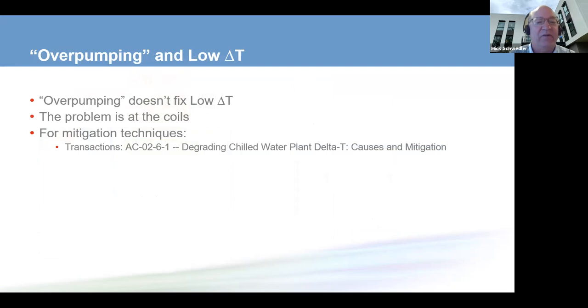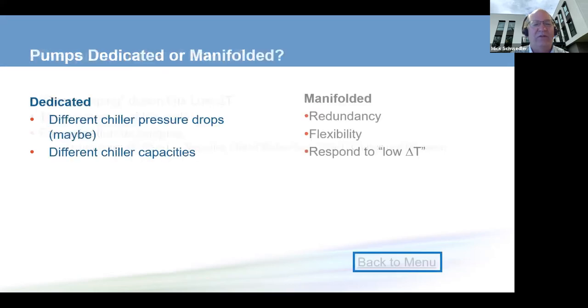There's an ASHRAE Transactions paper on degrading chilled water plant delta T's, causes and mitigation, that is available. Since it's a Transactions paper, it is for pay. Our company didn't write it. A consulting engineer out on the West Coast did. It's an excellent treatise on the causes of your low delta T, and also how we can fix those. So we talked about the advantages and disadvantages of dedicated and manifold pumps.